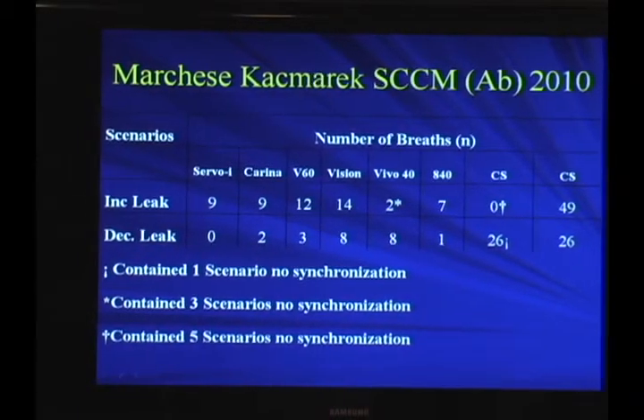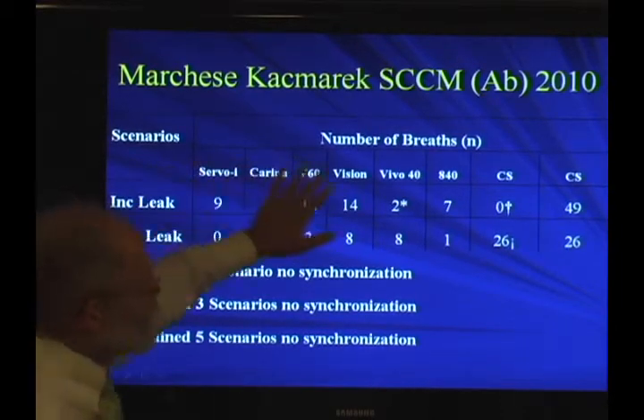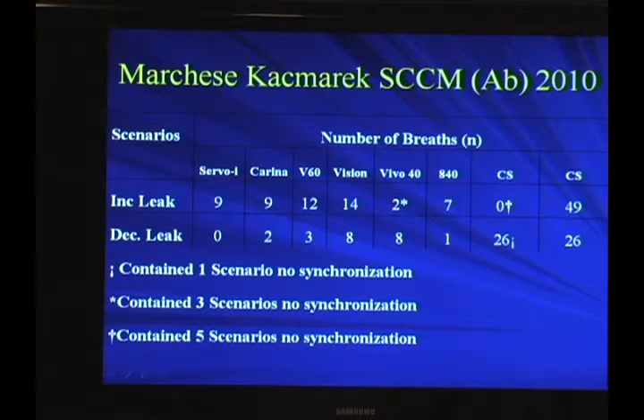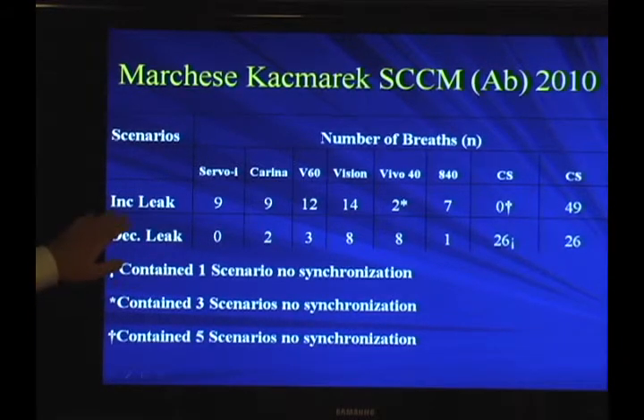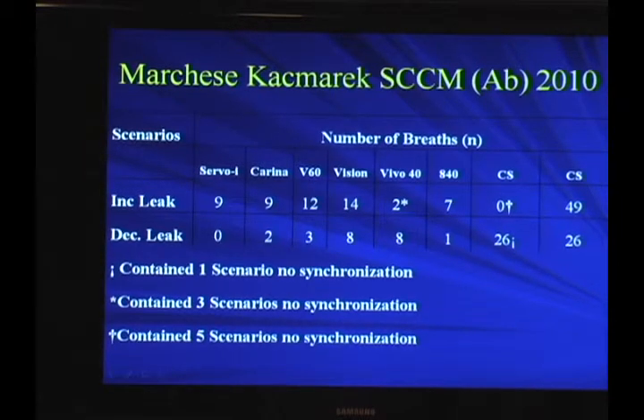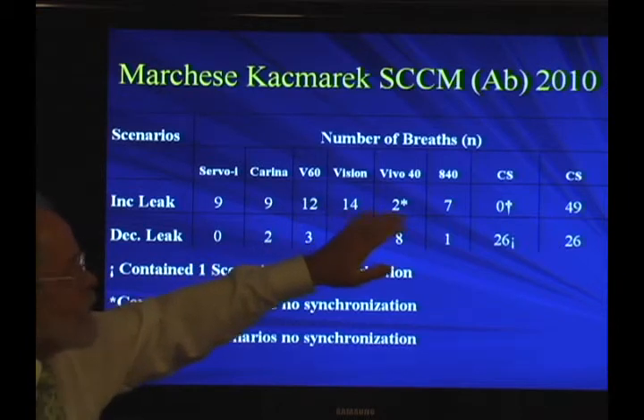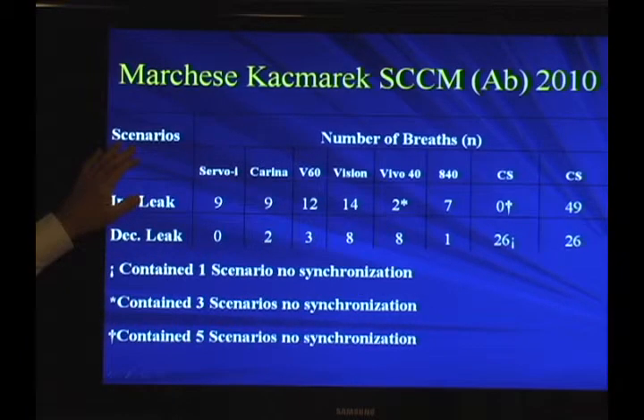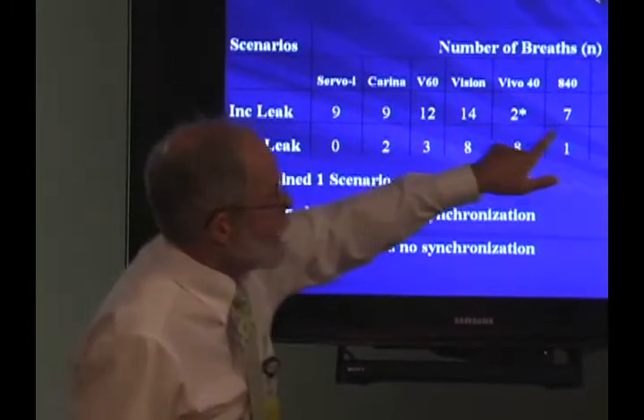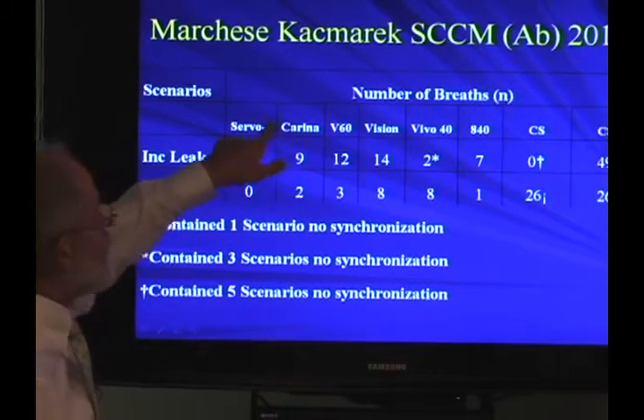This is data we abstracted at the Society of Critical Care Medicine meeting, comparing all of these ventilators in a lung model and their ability to compensate for leaks and deliver non-invasive ventilation. What we did was add 6 scenarios of increasing leak and 6 scenarios of decreasing leak, applied in a random manner. These represent the total number of breaths for the ventilator to reestablish the ventilatory pattern that existed before the leak was changed. In many cases, the ventilators were able to accommodate on the next breath or 2 breaths afterwards. With decreasing leaks, it is very rapid; it's easier for a ventilator to readjust to a decreasing leak than to an increasing leak. But look at the Servo-I and the 840 compared to these 4, which are all non-invasive ventilators.